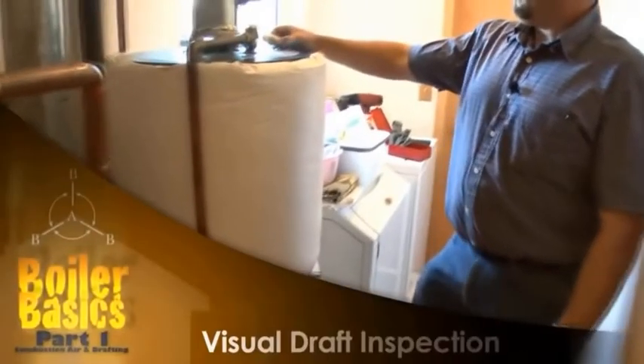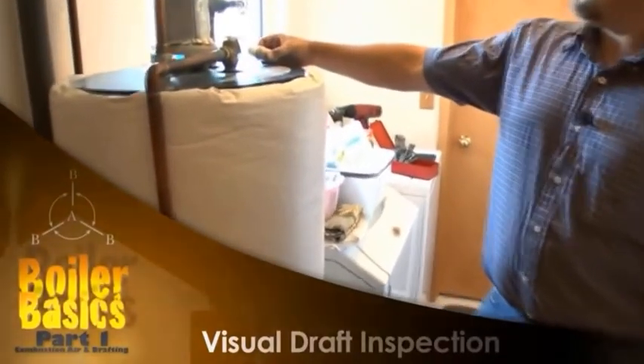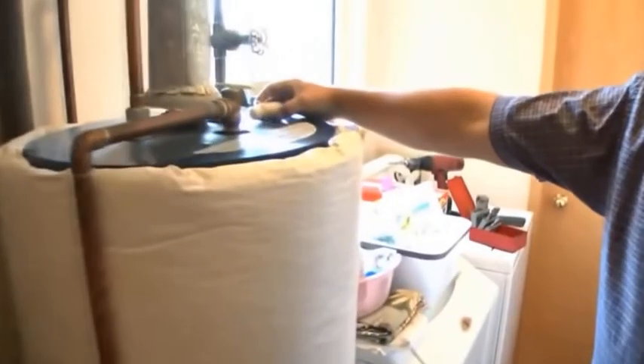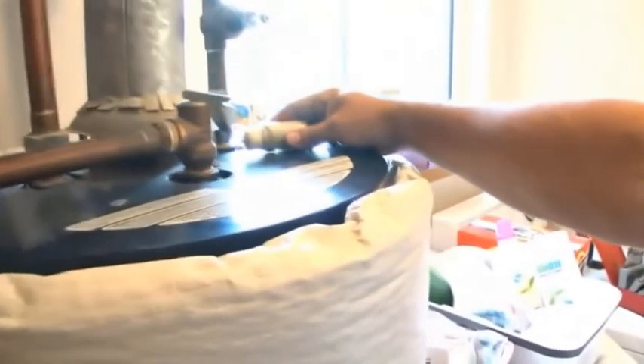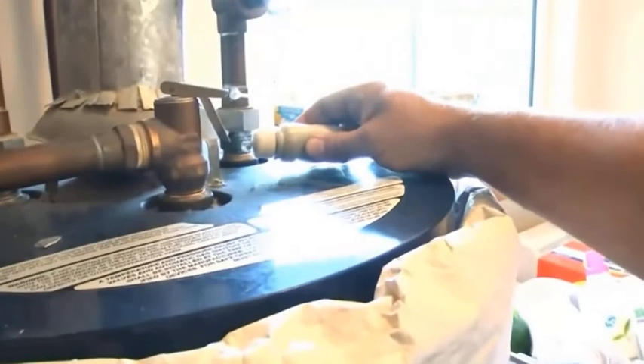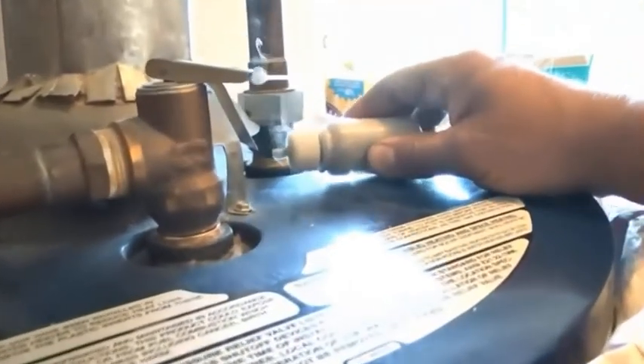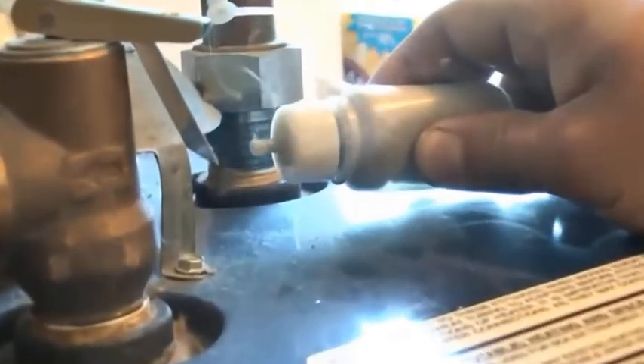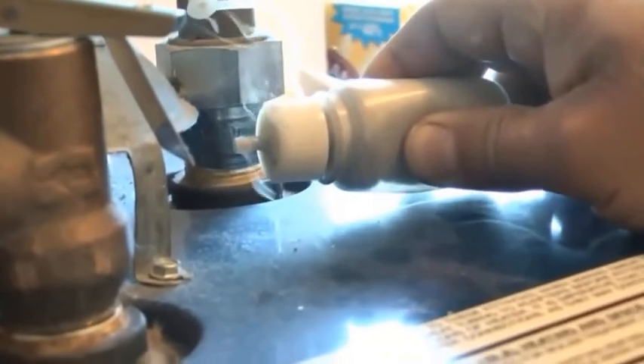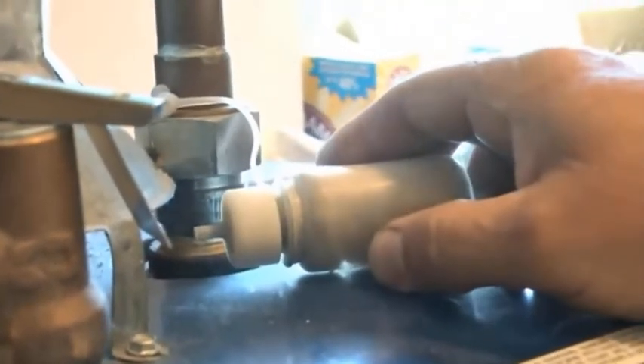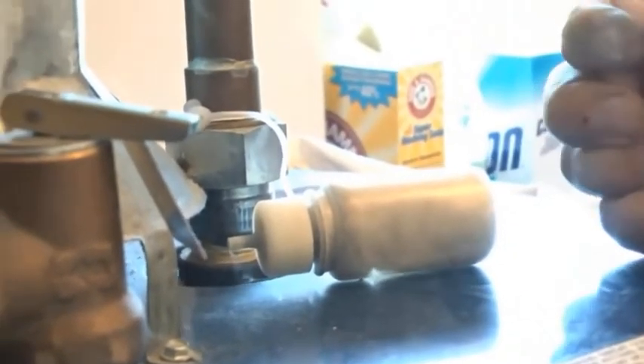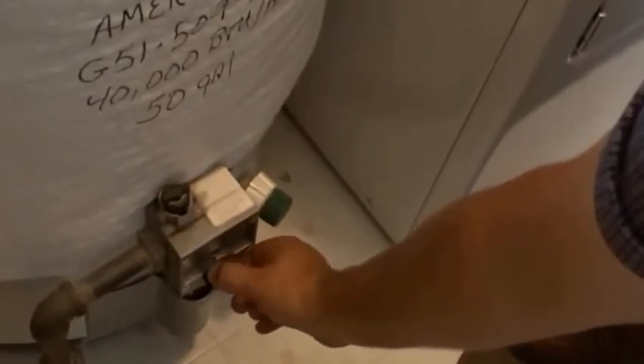We can also just use our smoke detector, or our smoke, and put it by the flue. Okay, now I don't have this running right now, but normally this would not be backdrafting, and it's backdrafting right now. What we're going to do is turn on our appliance, and it needs to stop backdrafting within 1 minute.